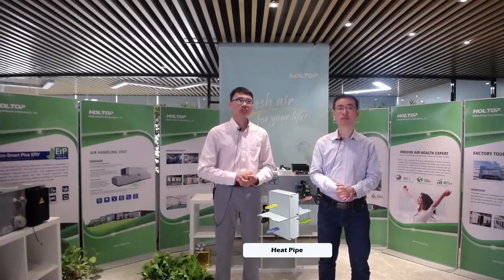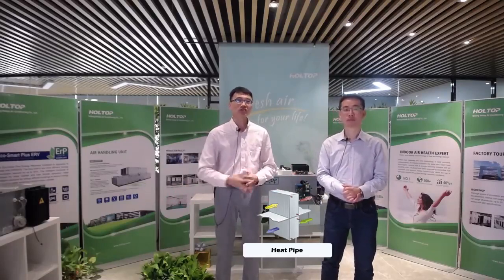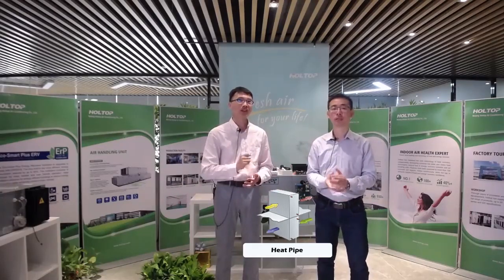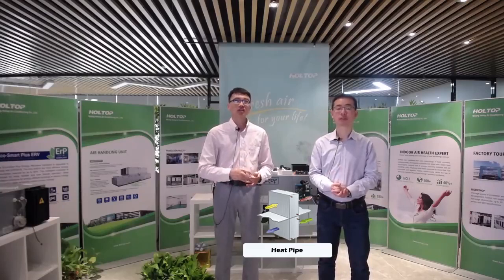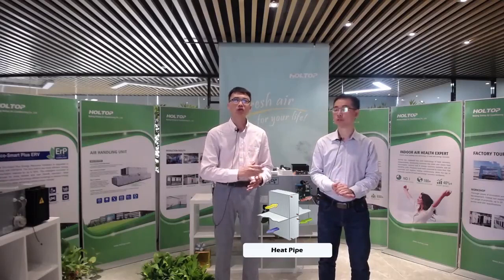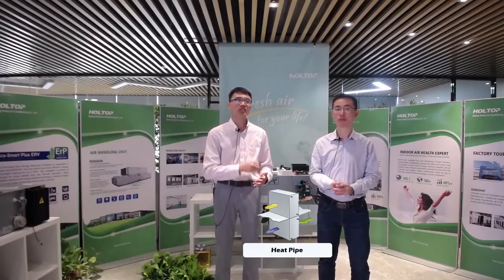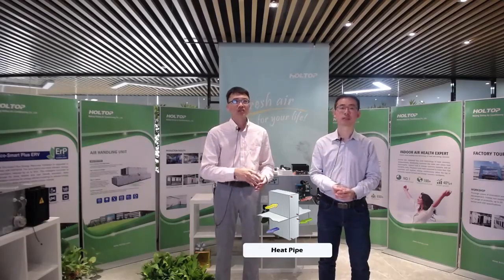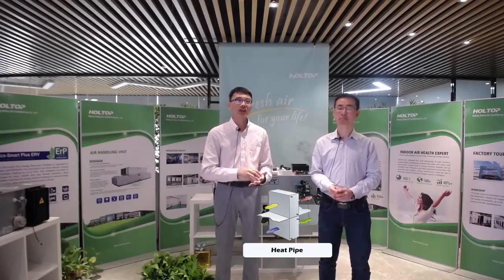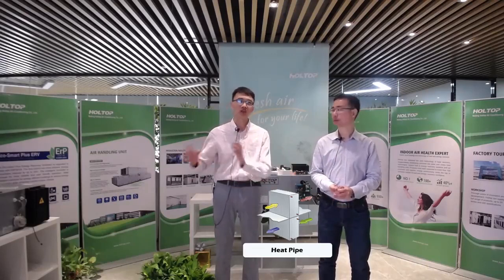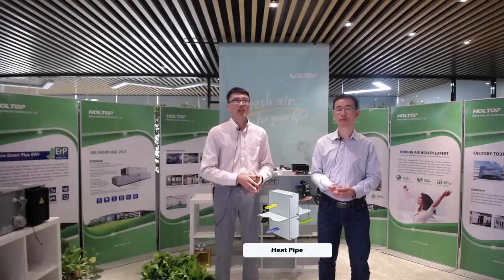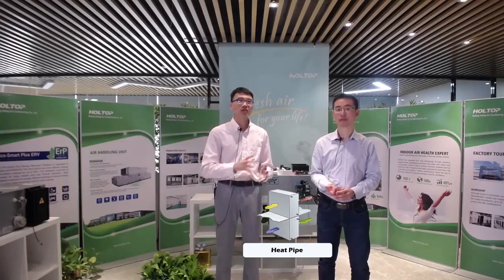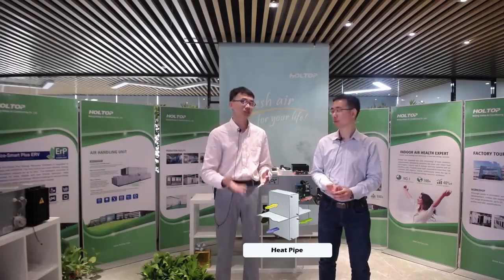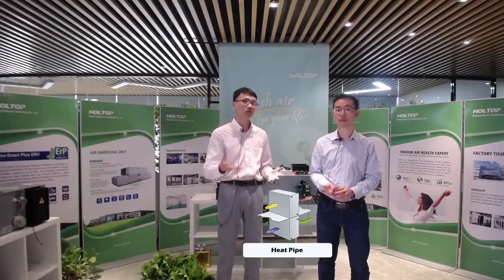And we have several key features for this one. The first one is the low air liquid resistance. Less condensing water and anti-corrosion for copper pipe and hydrophilic aluminum fin. Number 2 is no air leakage and cross-contamination, because the exhaust side and the supply side are totally separate. And number 3, it is free of maintenance, so we don't need any maintenance work for this one.